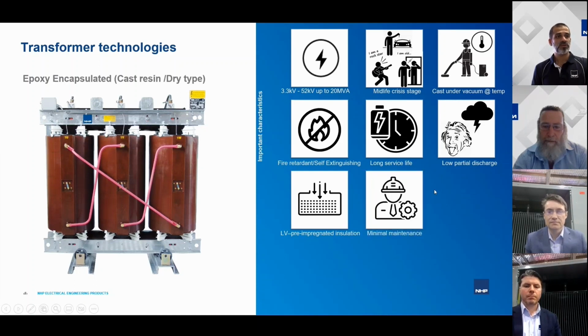Okay, now thanks, Dimitri. What are the typical maintenance requirements for cast resin transformers? Yeah, so typical maintenance requirements will really depend on the installation environment. Of course, for every cast resin transformer, from time to time, the tightness of all the bolts has to be checked, and they need to be torqued to make sure there are no loose connections, especially in the core and so on.